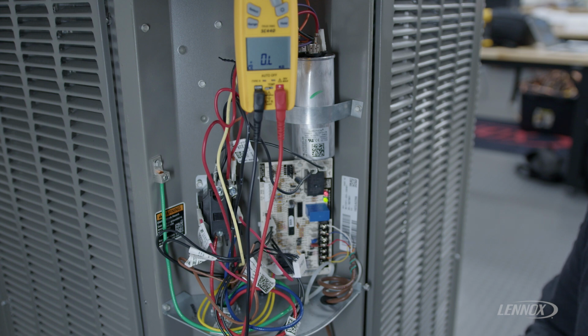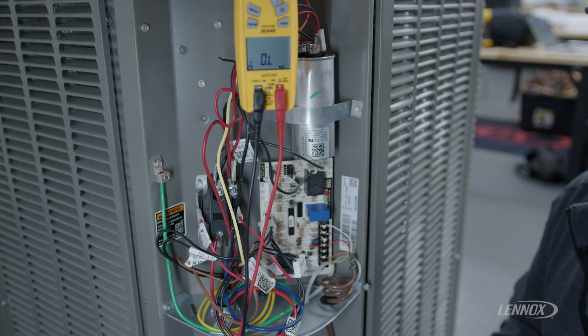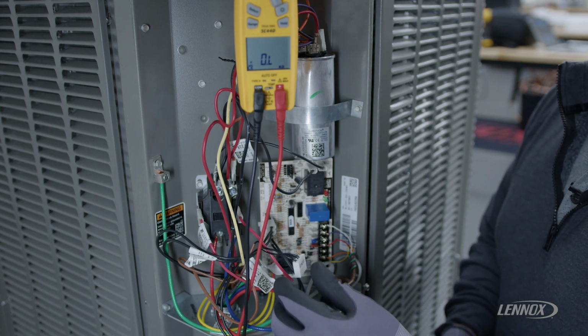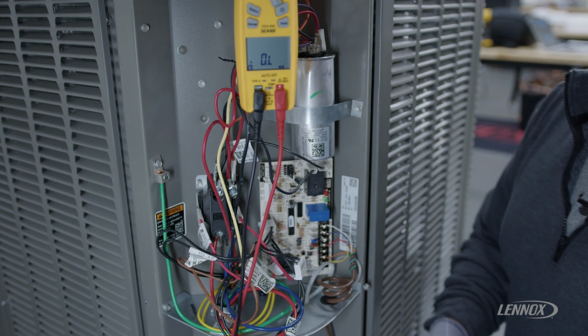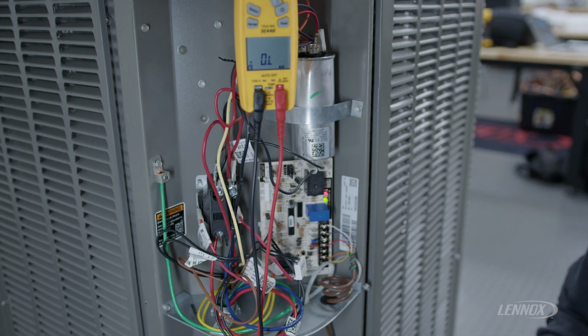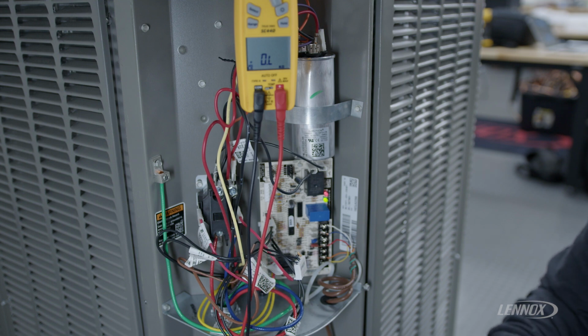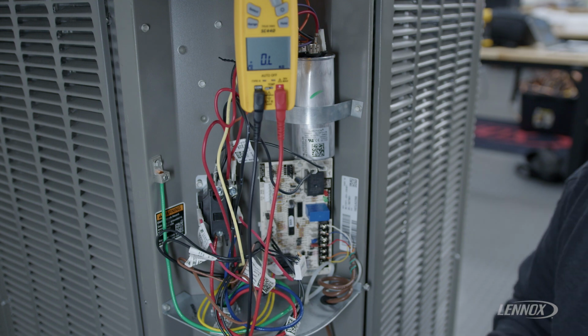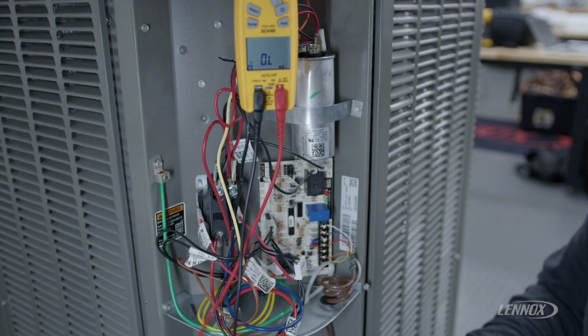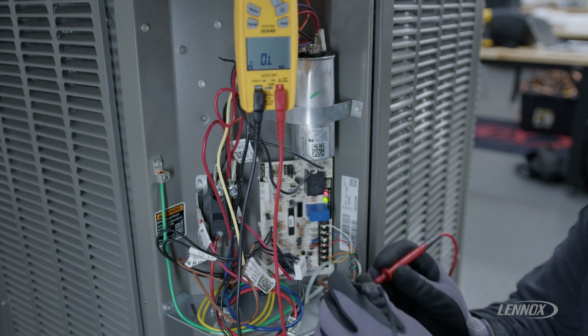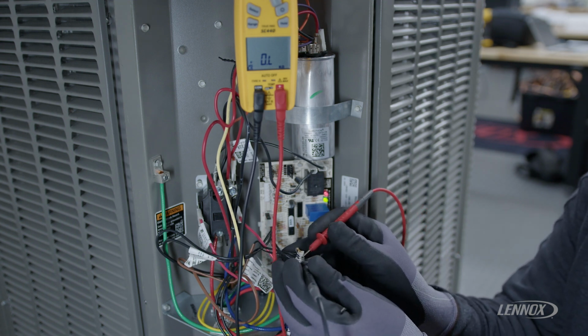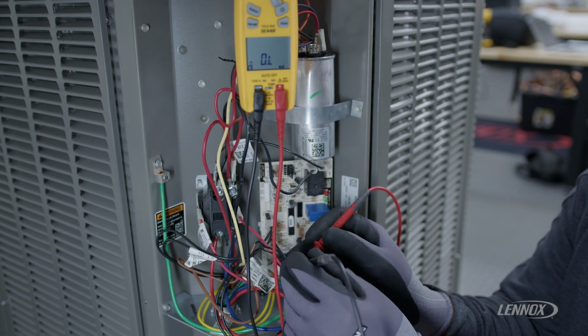To check this, we're going to unplug the harness cluster from the board, then ohm out that sensor with our meter set to ohms. This is a 10K resistive sensor, so once you get your readings, you'll compare it to a 10K sensor chart. We're going to put our meter leads on the back side of this plug.